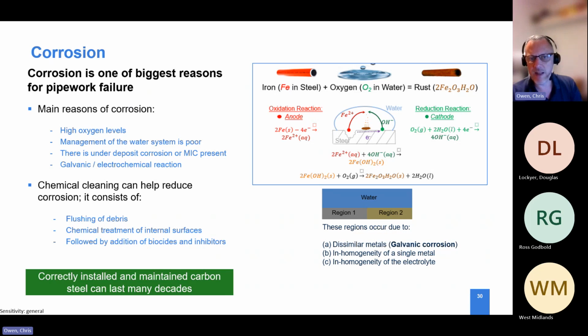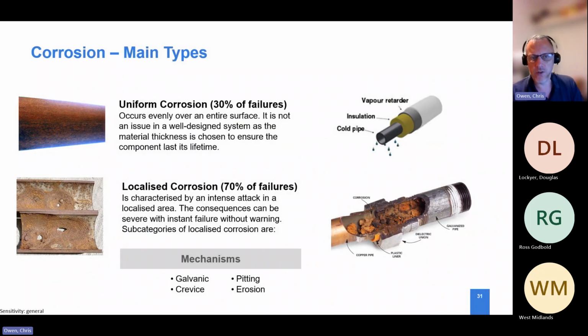So carbon steel has many decades of use in building services without issue. However, we are aware that when there are issues, normally it's not so much down to the tube, it's down to something which has happened in that installation, or something which has not been done, or an assumption which has been made which has been incorrect. And again, when we look at the types of corrosion failures, uniform corrosion is only about 30%. Localized corrosion is really where the main issues occur.